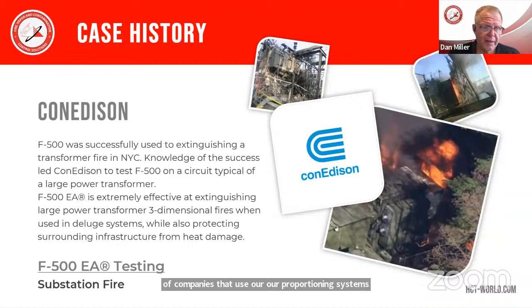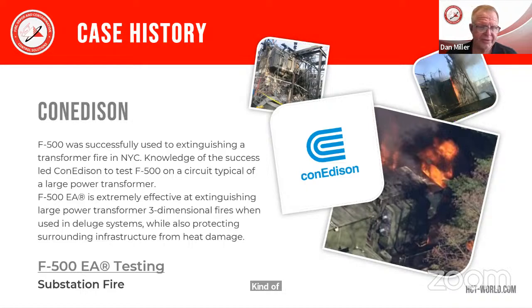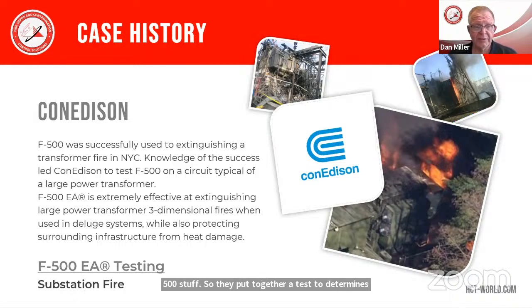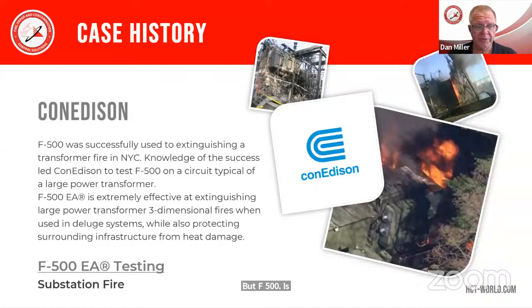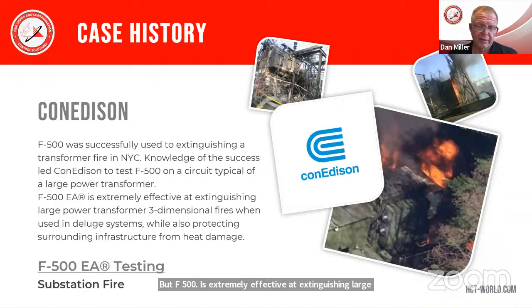Con Edison: F500 was successfully used in New York City to extinguish a fire in a large ground transformer. Con Edison caught wind of that and decided, well, we need to do some more testing with this F500 stuff. So they put together a test to determine standoff distances. They tested the F500 on a high power circuit up to 345,000 volts to establish appropriate standoff distances. However, that's for manual firefighting, but F500 is extremely effective at extinguishing large power transformers and the three-dimensional fires that they have as a major characteristic because of the cooling oil.